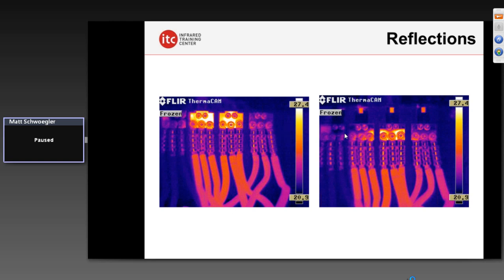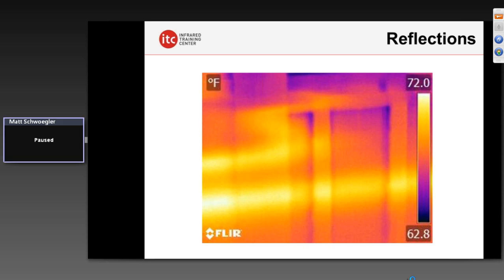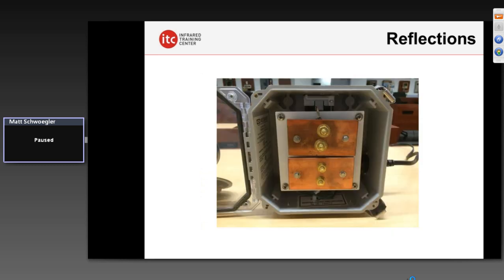Just by moving, we can identify the fact that this is a false hotspot — a thermal reflection, something we have to deal with, and that's why we emphasize it in training. Here we also see a thermal reflection off a wood floor in a residential home — the image of a door reflecting off the floor while we're trying to find radiant floor heating. Everything emits infrared radiation, and depending on the emissivity and reflectivity of the surface, it can make things very confusing. We have to understand these important relationships.